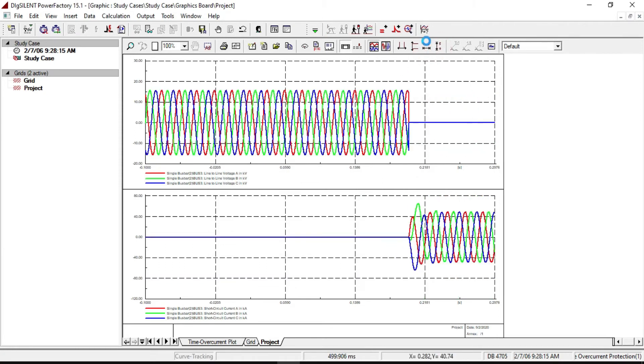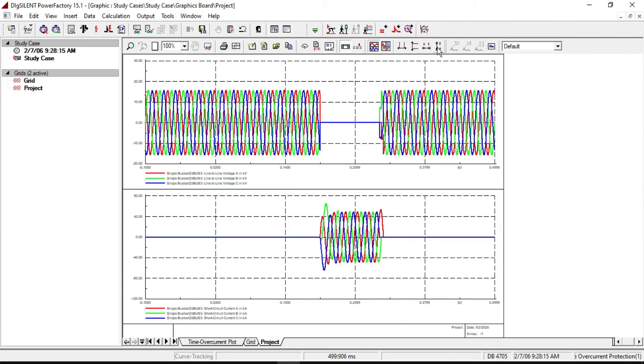Click on Autoscale — that is how our waveforms look. As you can see, from 0 to 0.2 seconds our system is operating normally. But from 0.2 to 0.3 seconds there is a short circuit event, the voltage system drops down, and the fault current is rising. After 0.3 seconds, the three-phase fault is cleared and the system returns to normal operation.